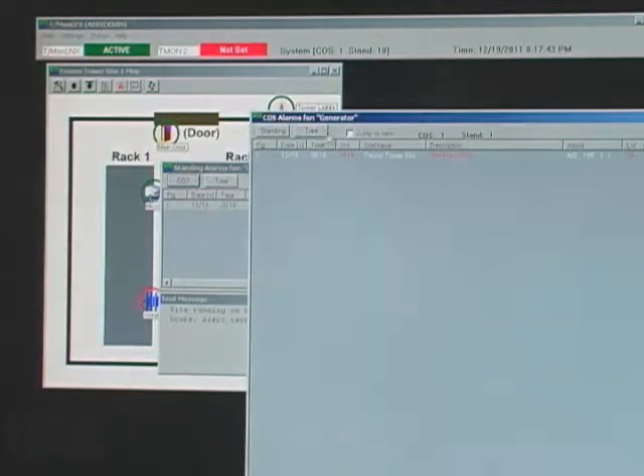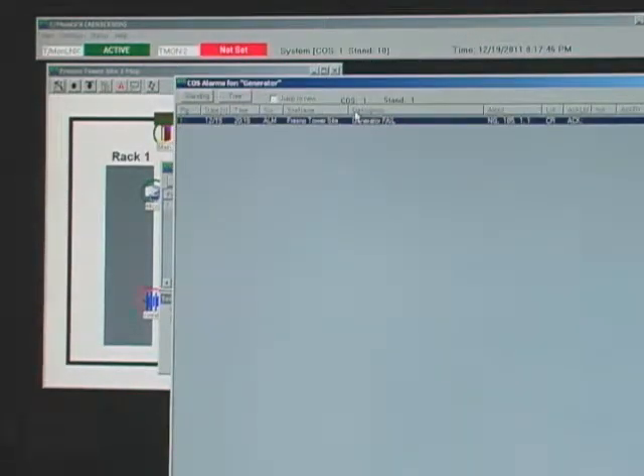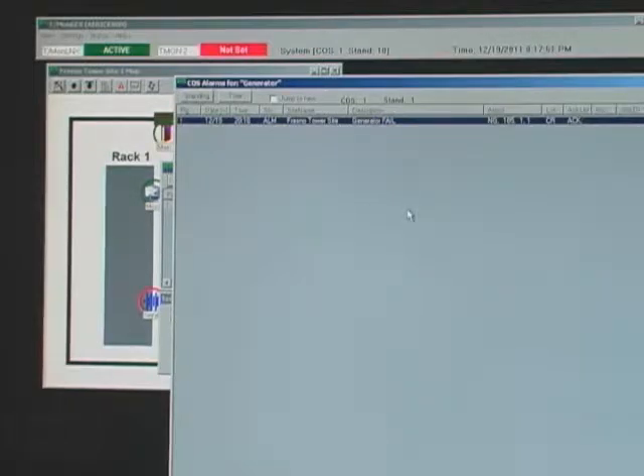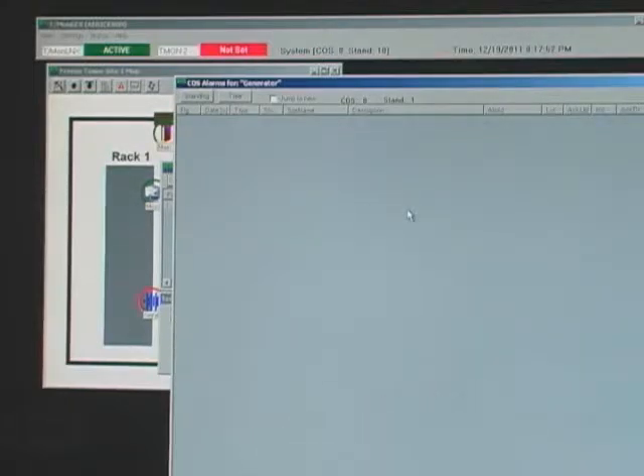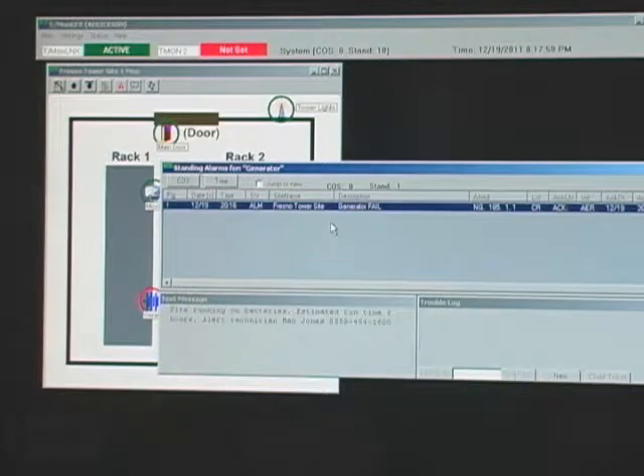So I get all the information I need to address that alarm. I can go to the COS screen and indicate that yes, I, this user, am going to acknowledge this change of state, and I'm going to address it. So I'm going to hit Enter, and it'll vanish from the change of state, but it never vanishes from the standing screen until the situation is repaired and the alarm actually does clear. So we'll see that now.